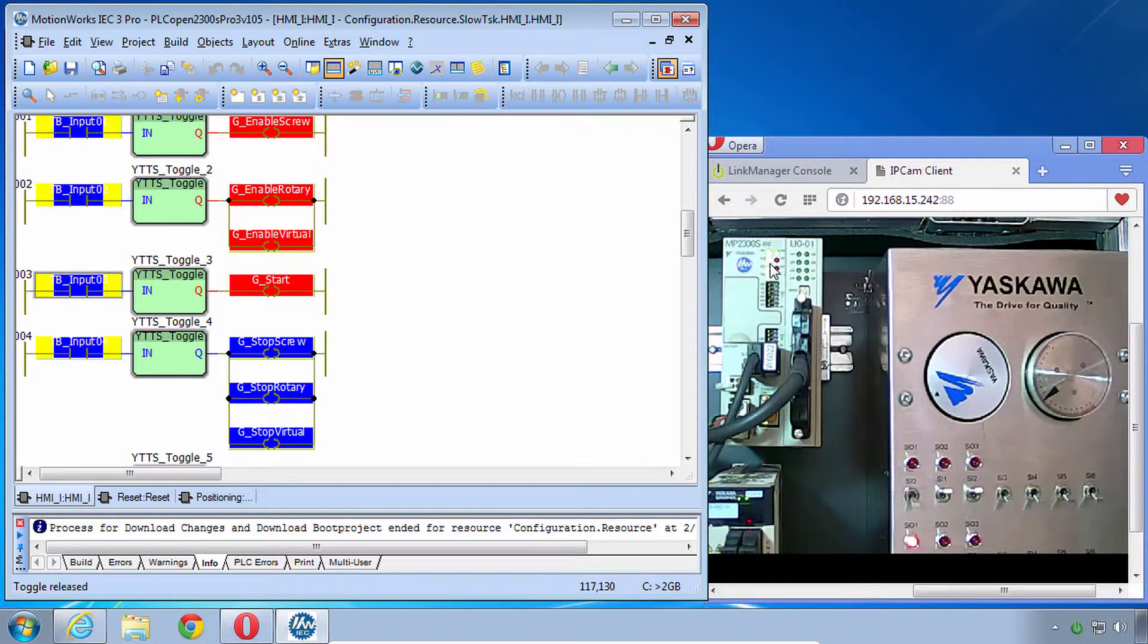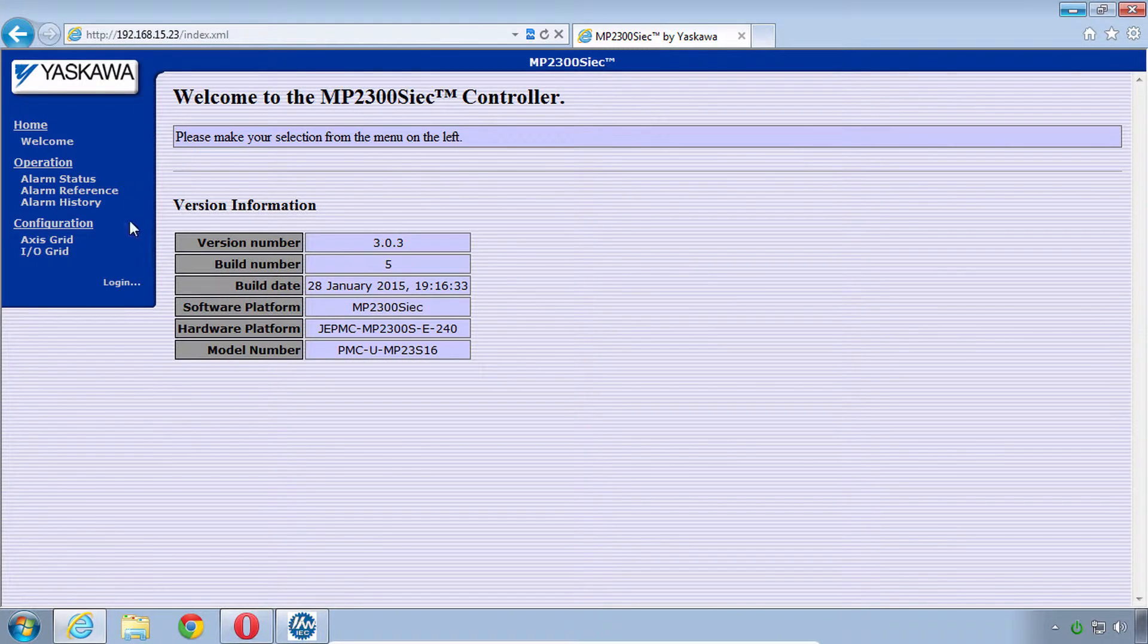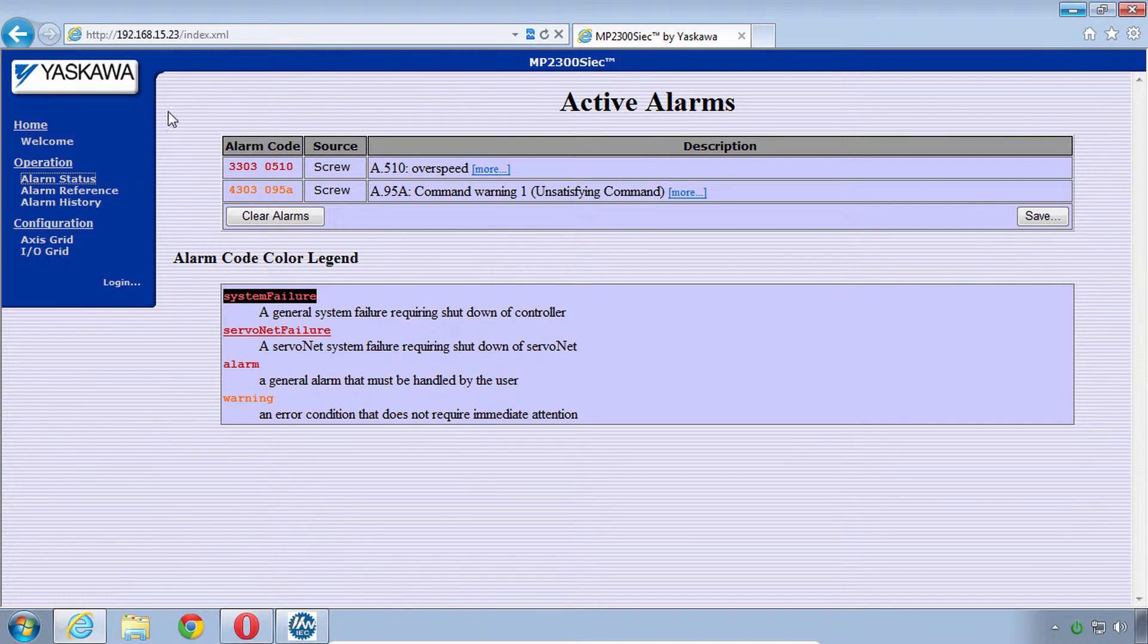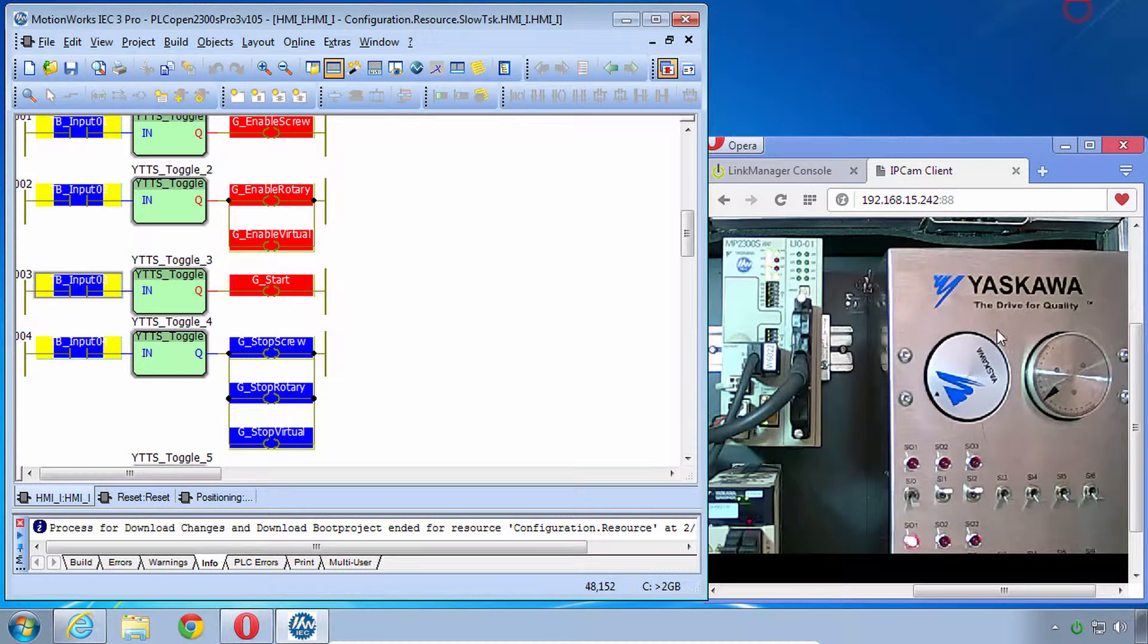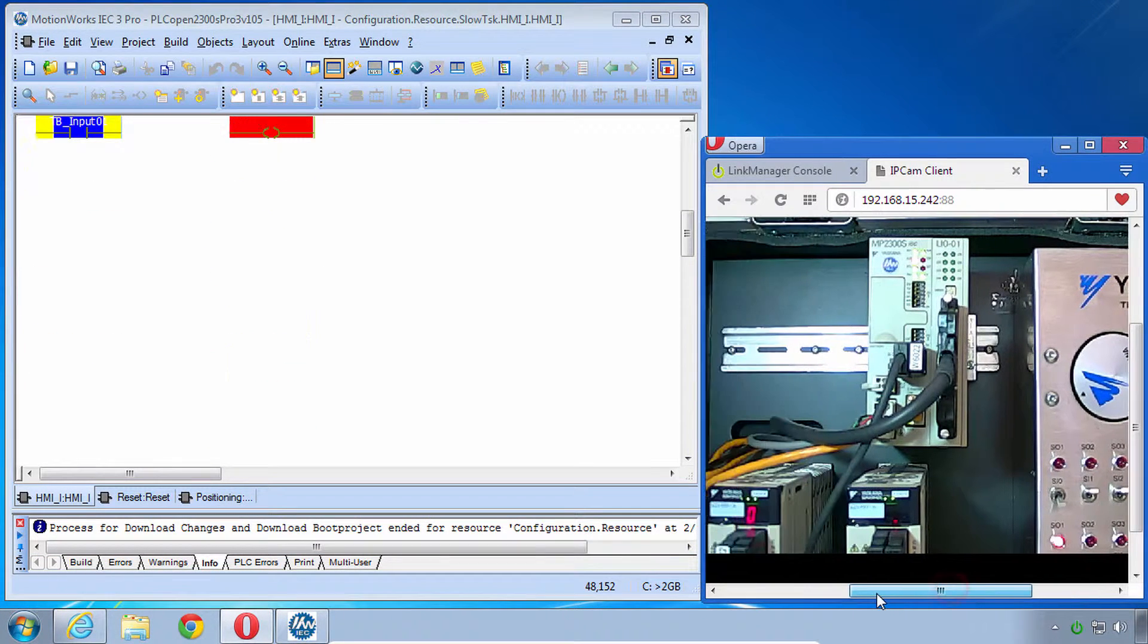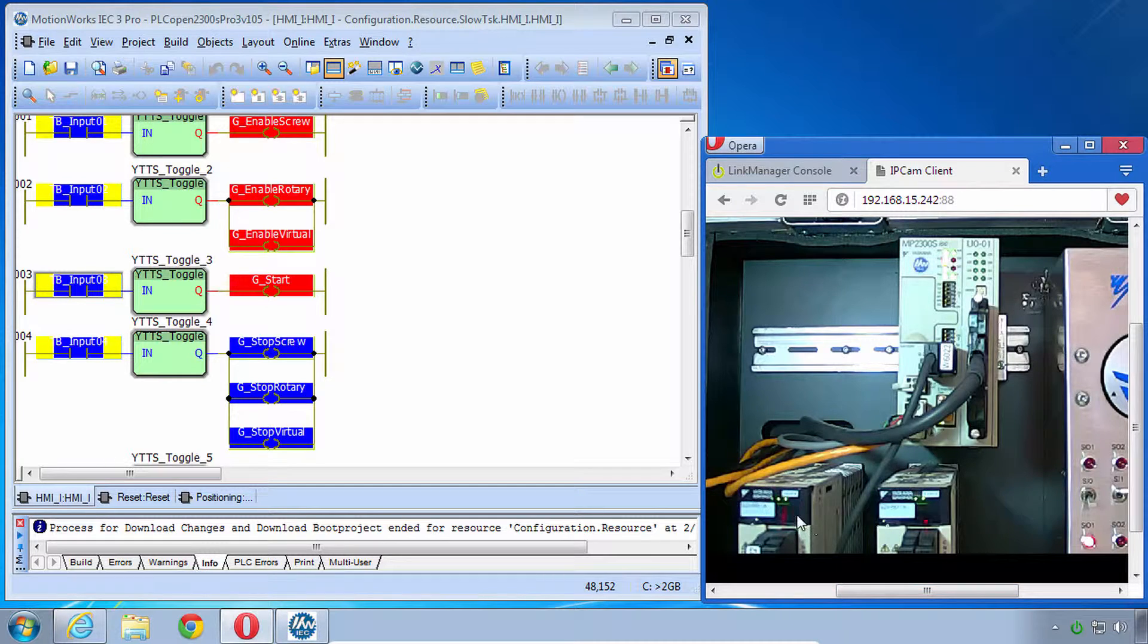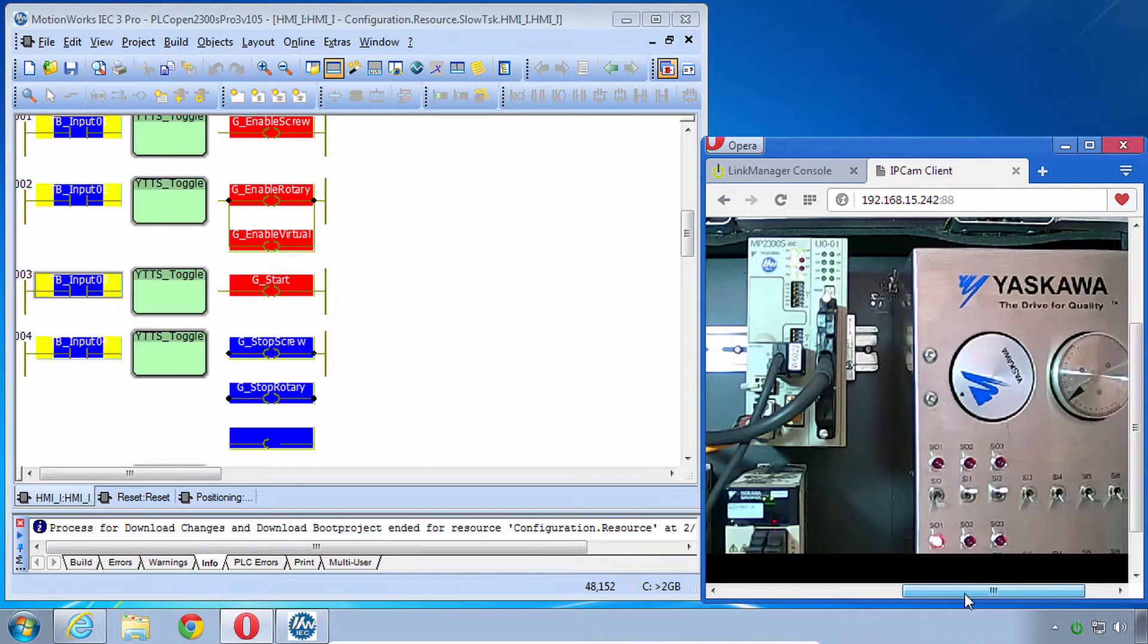But there's this alarm light on. You can kind of tell it's red. There's a controller alarm. Definitely in the web page, if you wanted to look at the alarm status, you could see that there is an alarm A510. That's over speed. If you still don't believe me, you could look at the servo itself. It's flashing A.510. So we've got an over speed A510.